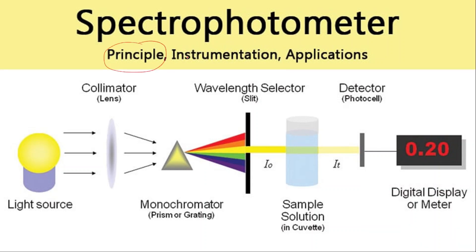Now we will discuss the instrumentation principle and its application. The spectrophotometer has a light source, then a collimator lens, and then a monochromator.